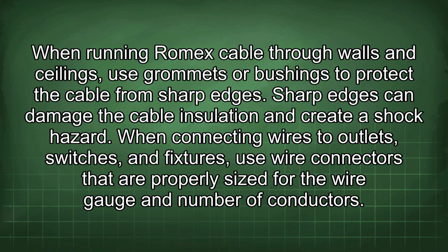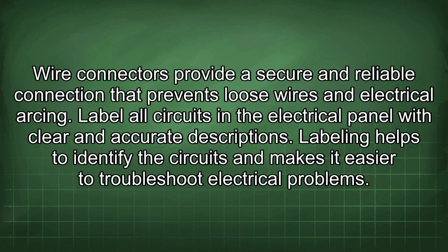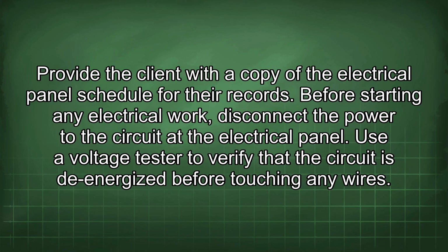When connecting wires to outlets, switches, and fixtures, use wire connectors that are properly sized for the wire gauge and number of conductors. Wire connectors provide a secure and reliable connection that prevents loose wires and electrical arcing. Label all circuits in the electrical panel with clear and accurate descriptions. Labeling helps to identify the circuits and makes it easier to troubleshoot electrical problems. Provide the client with a copy of the electrical panel schedule for their records.